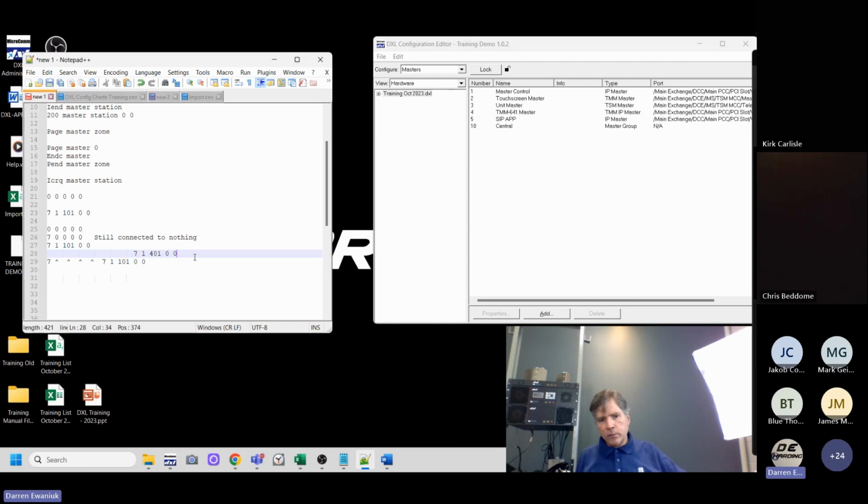It writes a value into a handshake register on the DXL system. The act of writing any value, it doesn't matter what the value is, into that handshake register will tell the DXL to send you any new update. So if there's another message waiting to be sent, it can be sent right away. So send a handshake every time you process a message that you receive, and the DXL system will send you the next one. So those are the two mechanisms. The poll is a little simpler to do, but there's a lot of network traffic because it's always copying data to and from the DXL system.